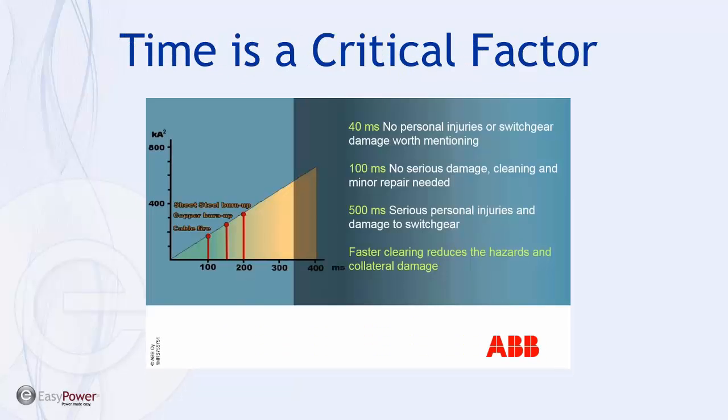As you can see, time is the critical factor. With 40 milliseconds, you don't have much damage or no personal injuries worth mentioning. You go a little bit faster, a little bit slower than that, and now you're starting to get into some damage and some other problems.